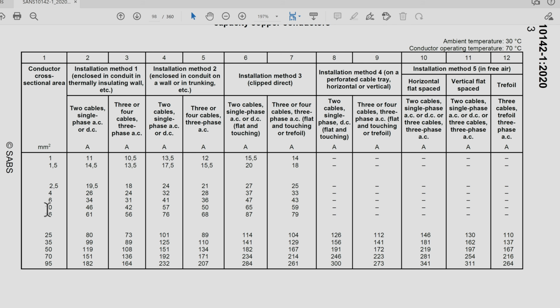For example, if you just look at a 10 millimeter cable, it should be able to handle 46 amps. That is, if it is enclosed in a conduit in a wall. But notice that that goes up to 57 amps if it is in trunking on a wall, not in a wall. And if it is just clipped, meaning that there's nothing around the cable, we can now go up to 65 amps. So the layout of the cable is very important in how we specify the cable. And also, I'm going to be using copper cable. If it is aluminium cable, you need to derate these or lower these values significantly.